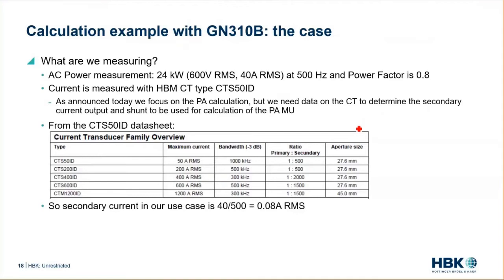Let's take a look at our use case. What are we measuring? We are measuring AC power: 24 kilowatts at 600 volts and 40 amps RMS, at a frequency of 500 hertz and a power factor of 0.8.